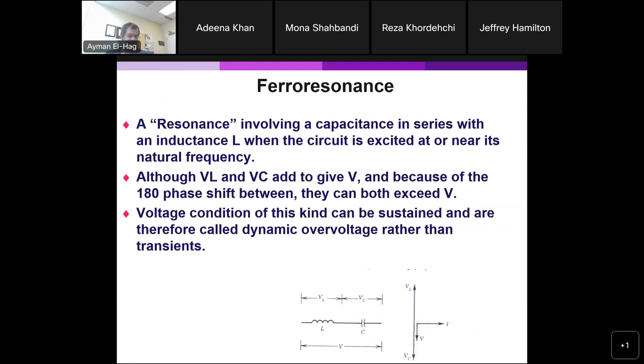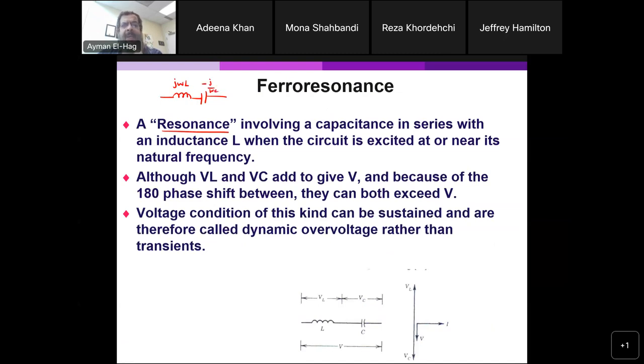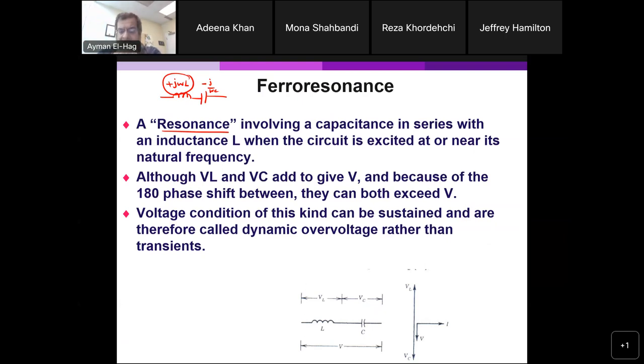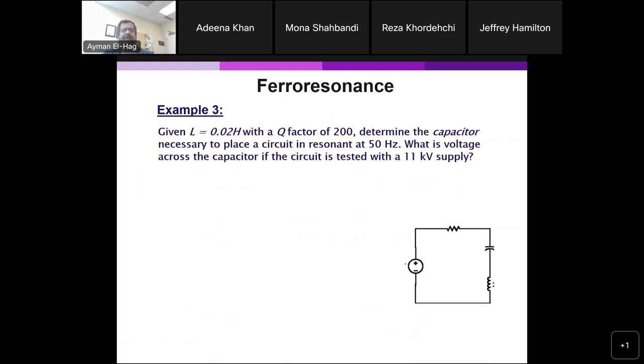The last abnormal transient is ferroresonance. What is ferroresonance? Resonance is a concept we know: when you have an inductor and capacitor — mainly in series — with reactances jωL and −j/ωC, at a certain frequency they cancel each other and become like a short circuit, minimizing the impedance in the system and leading to many practical problems. Ferroresonance involves the resonance between the system capacitance and the core of a transformer — 'ferro' comes from ferrite, the material used in the magnetic circuit.